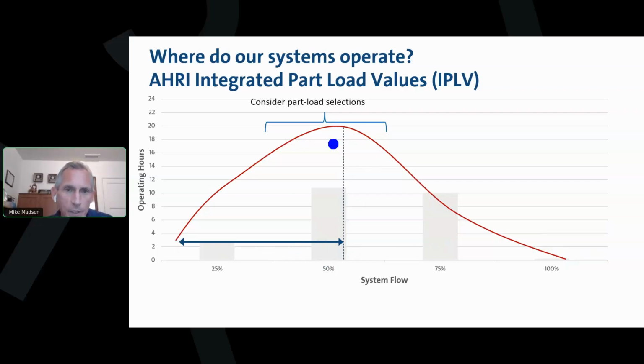So what we want to do is we want to start selecting our equipment to a load profile. And that's very easy to do. Most of our softwares include an option where we can actually select equipment based on a load profile instead of picking something that's very efficient at this full load condition, but then we spend only 3% of the season operating there. So for the engineers on the call, we would actually start to schedule part load efficiencies for pumping equipment like you do for chillers. And you're going to get better, more efficient selections that way.